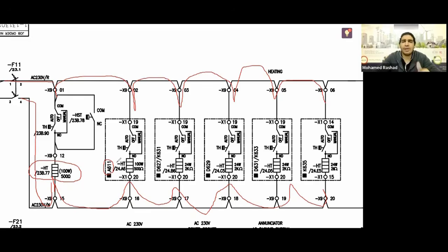As for the heater, where is it located? It's located in the mechanism box of the breaker, in the mechanism box of the 3-position switch, and in the mechanism box of the other disconnector as well. Each mechanism box also contains control circuits and a motor inside, so each one also needs a heater.